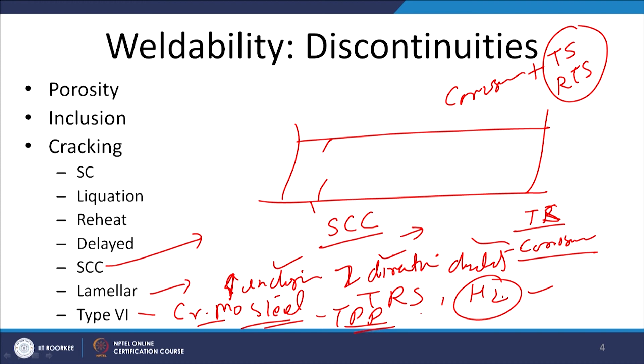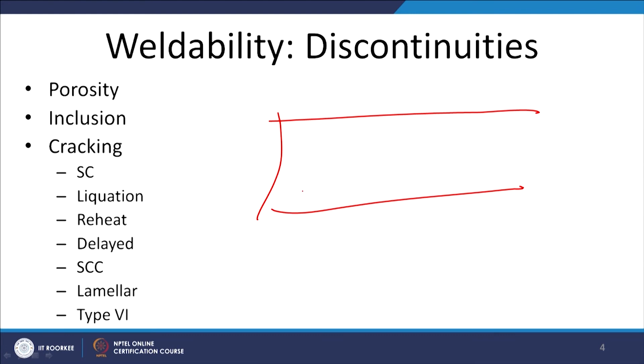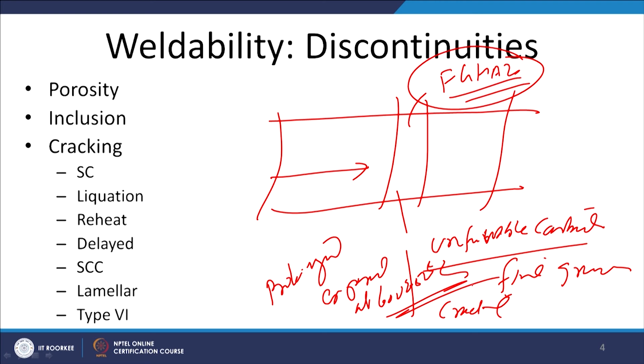Type 4 cracking is typically observed in chromium molybdenum steel weld joints. These are the steel weld joints which are used in thermal power plants in the temperature range of 600 to 650 degree centigrade. When such weld joints are used at a high temperature, a fine grained HAZ zone is formed. In this region, on prolonged exposure at a high temperature, formation of unfavorable carbides at the grain boundaries of the fine grains promotes cracking in the region away from the fusion boundary, wherever the fine grained heat affected zone is present. That cracking occurs after a prolonged exposure at a high temperature, maybe 600 to 650 degree centigrade. So, this is type 4 cracking. The different types of cracking will be observed in different types of steels.